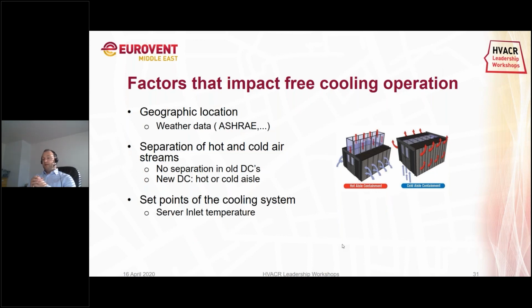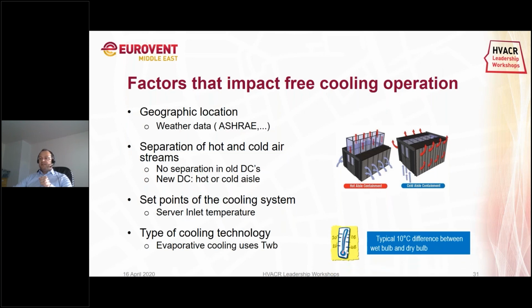And the next point that is very important to pay attention to is the set point of your cooling system. So the server inlet temperature. It depends on the energy consumption and also on the complete architectural design of your data center. And last but not least, the type of cooling technology is very important. As we mentioned, evaporative cooling is using wet bulb temperatures. Typically, wet bulb is 10 degrees lower than the dry bulb. So with evaporative cooling, you can easily see that you can achieve lower temperatures. So you can provide much lower condenser temperatures to your chiller and can achieve the biggest savings.